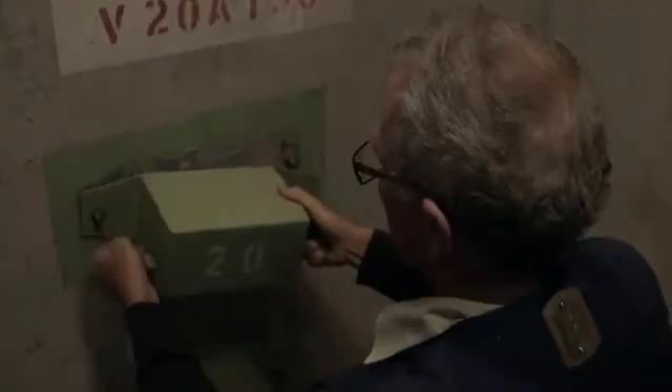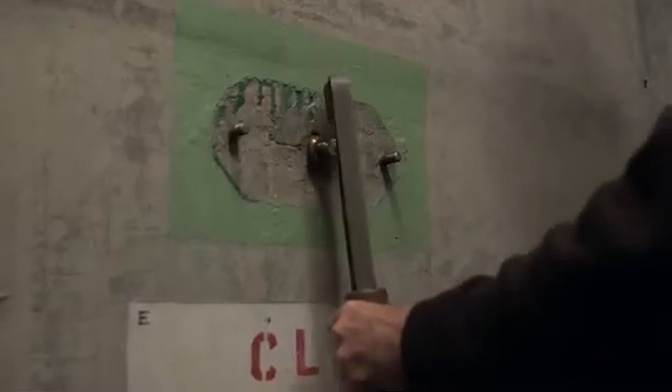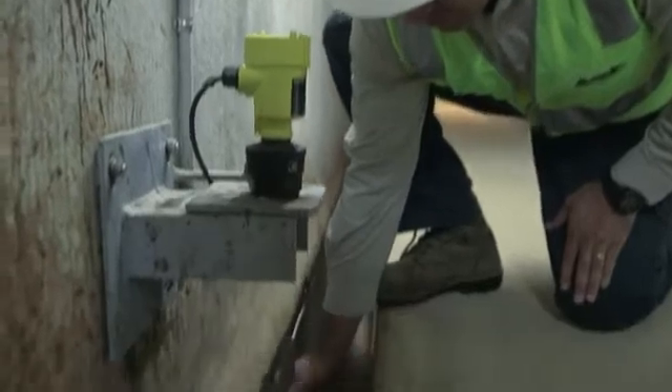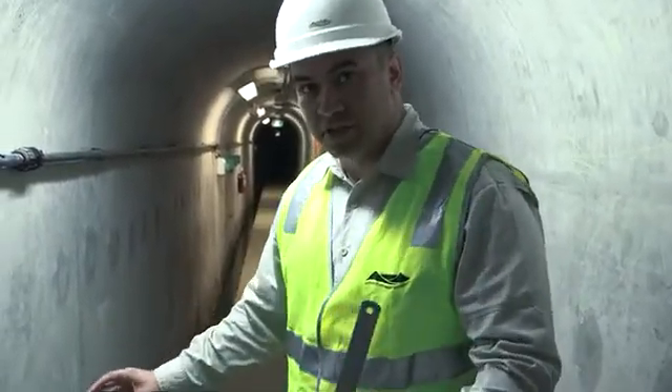The dam is built in blocks, so we have these markers and stations on various blocks. Any small movement of the dam forward or back because of changing water pressure will be indicated by the movement of the walls at a different level. Concrete is porous, so when the engineers designed it they knew how much water was going to pass through the structure itself. Within the Warragamba Dam structure we have V-notches located through crucial points throughout the dam. The V-notches and the flow measurements allow us to understand how the dam is performing — this VG11 is a collection of water for this section or block of the dam, measuring all the flows up to this point.